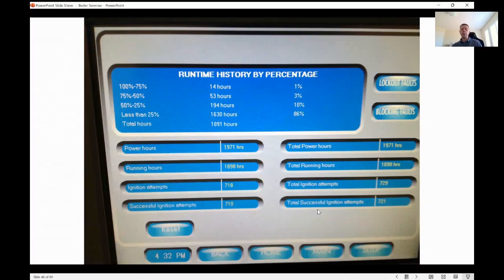This was actually an office building in Toronto, just off the 401 there. And after one heating season, I happened to drop by there and took a look at this, and I just snapped the picture because I thought it was cool. And most of them, once again, are like this. Most of them are actually 70% or higher, I find. So with this situation here, in this heating season, this boiler operated at less than 25% modulation 86% of the time. So 86% of the heating season, this boiler had turned on, ramping up, ramping down, giving the system exactly what it needed without shutting off.